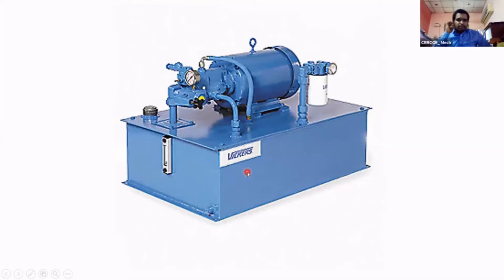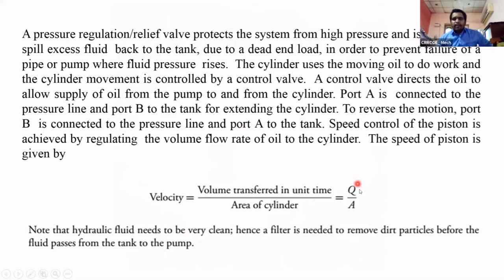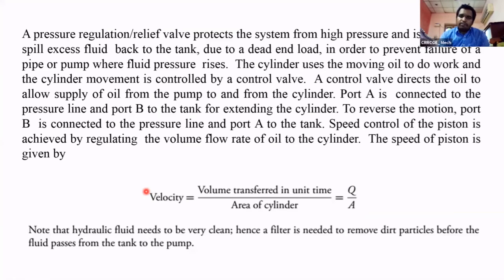This is the real hydraulic power system - the reservoir, motor, pump, input/output pipes, and pressure gauges. We can also control the speed of the piston using the relation: velocity equals flow rate divided by area. By controlling the flow rate, we can control the velocity. If fluid is sent at high flow rate, the piston movement speed rises; if flow rate is less, the piston velocity decreases.